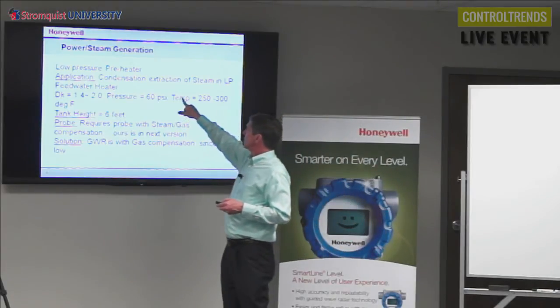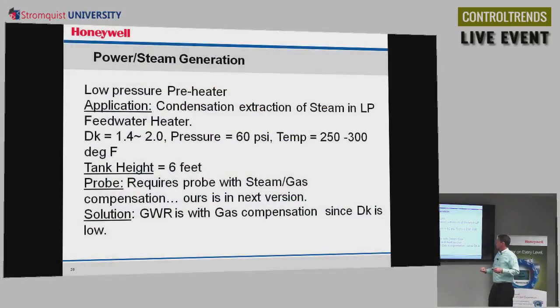So it's the condensation, extraction of steam, and low pressure feed water heater. The dielectric constant is 1.4 to 2. And remember, we'd said that the dielectric constant of water is 80. The reason it's so low in this application is because this water is aerated. There's a lot of air bubbles in there. That lowers the dielectric constant. So that makes it a challenging kind of application.